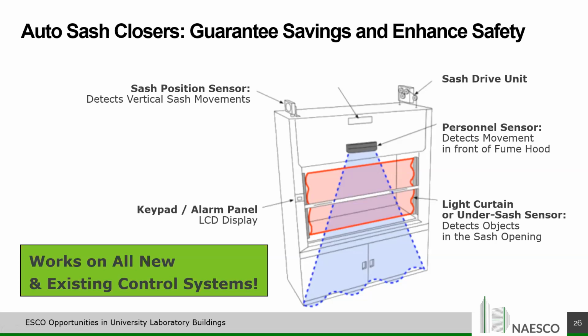Now, these are all the components that go into the auto sash closer. For example, we have a sash position sensor, which tells us where that sash is at all points in time. A personnel sensor will detect if anybody's standing in front of the hood or not. An under sash sensor is an IR laser beam that goes across the bottom of the sash handle, which will prevent the sash from closing on any obstruction that has been left in the fume hood itself. This guarantees that the fume hood will be as efficient as possible, whether someone is in front of it or not.